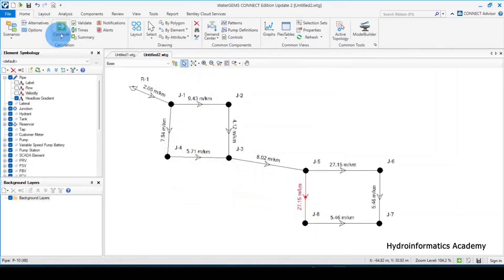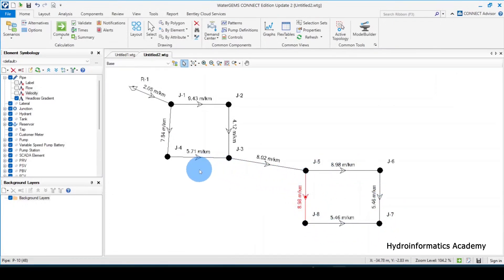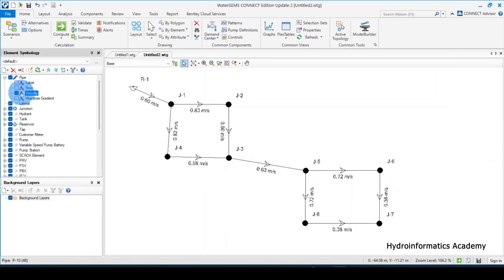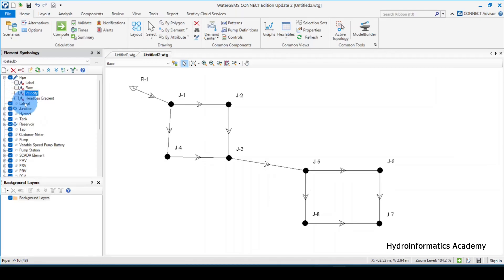With the pipes set back to 63 millimeters, let me run the model again. Okay, this is the situation we are having now — it's not that bad. Let me also re-activate the velocity annotation. You can see the velocity values — there are a few minor issues, but they are not that bad overall.